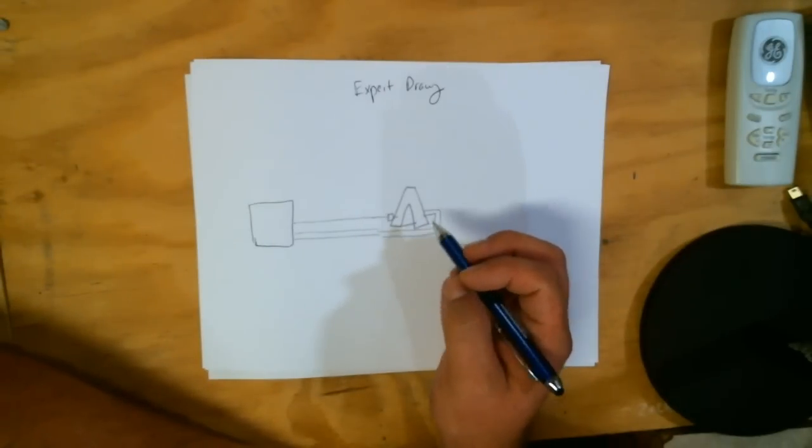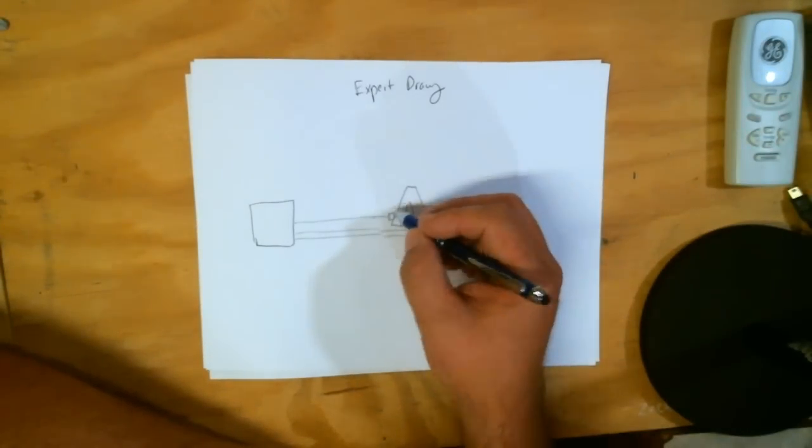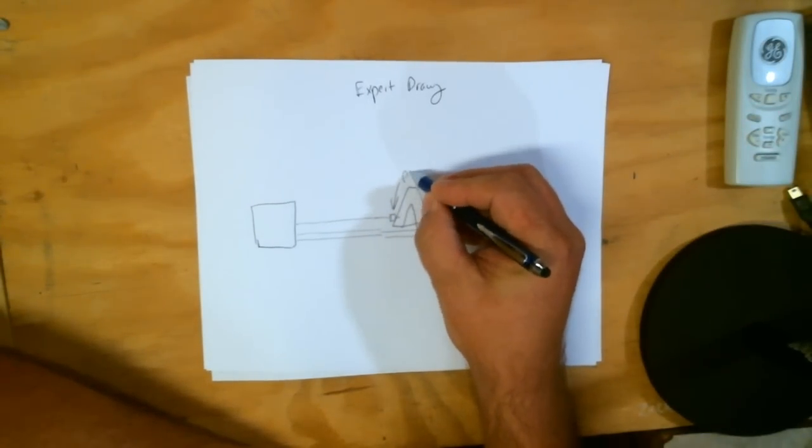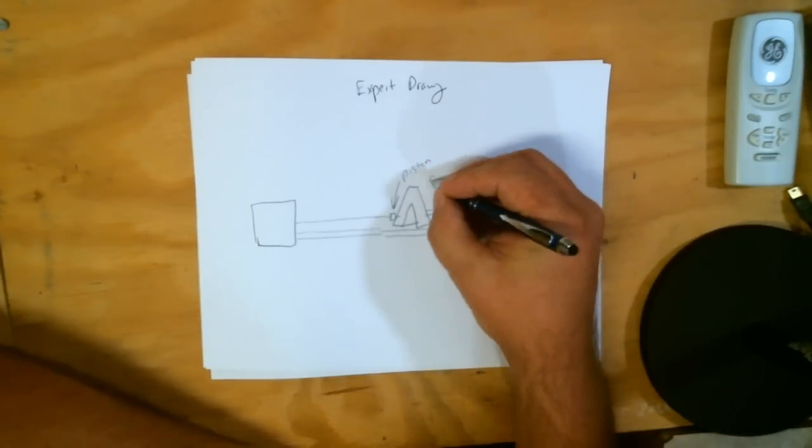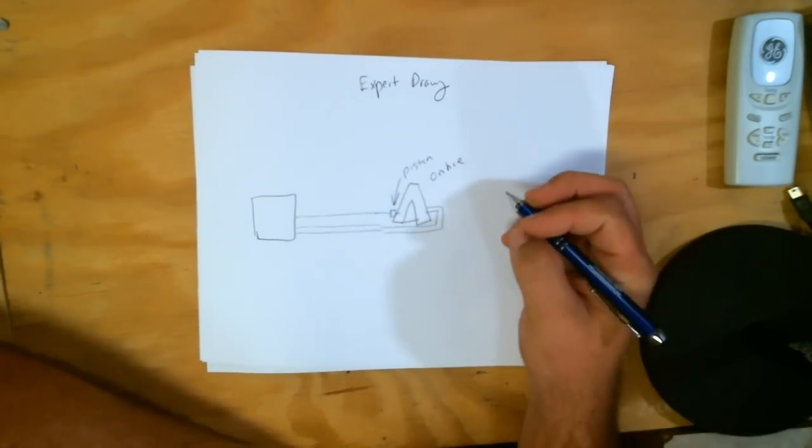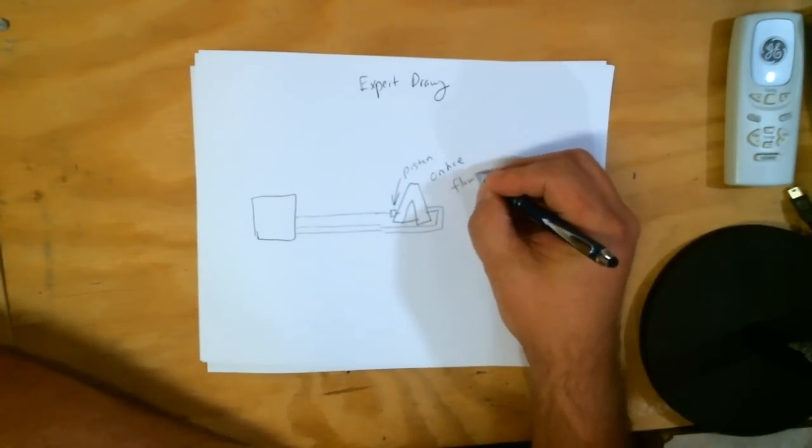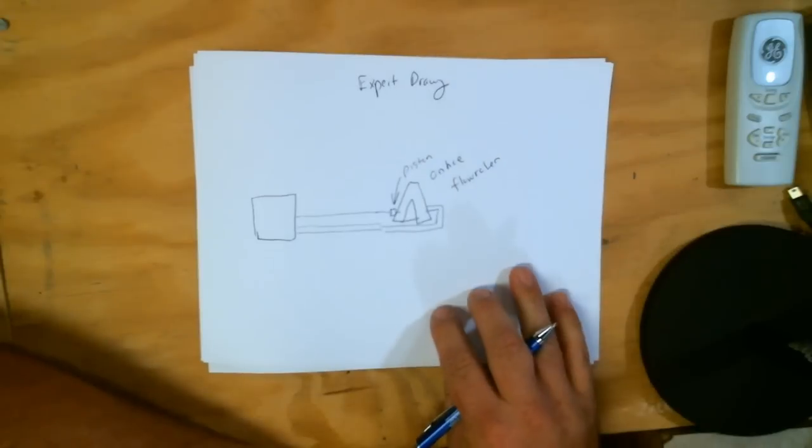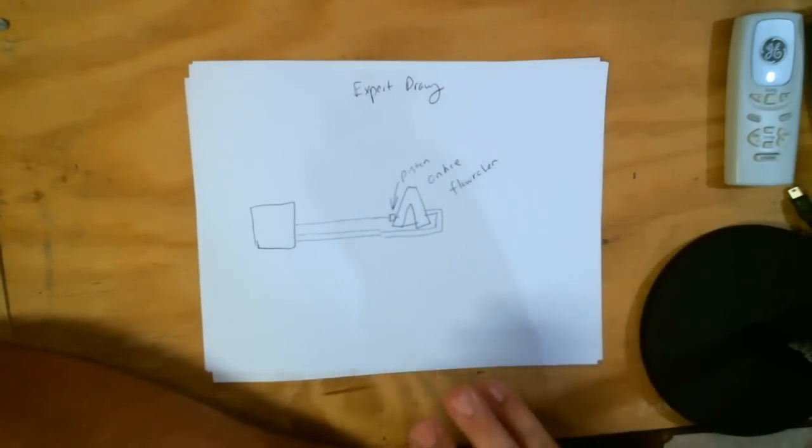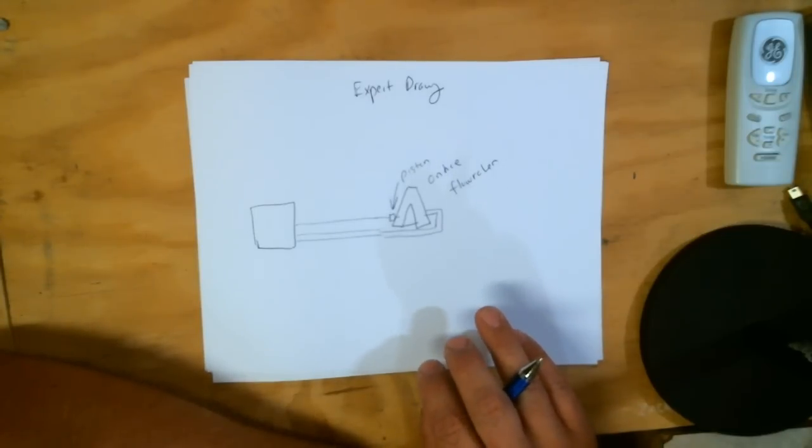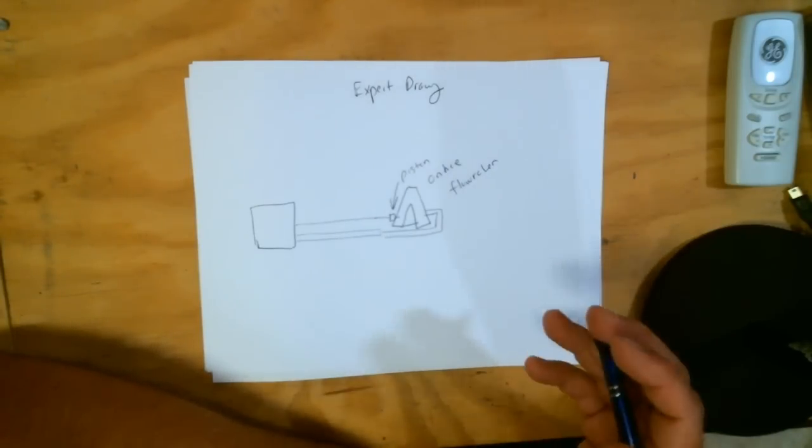So what I was talking about is back in the day when you got your matchups, and still today especially on the piston system - because this will be a piston right here, we're not talking about TXVs - piston, orifice, and flow rater are all the same thing. What we're talking about is when you have a mismatch system, not an unintentional mismatch but an intentional mismatch, meaning they are different capacities. So let's say we have a two ton outdoor unit.